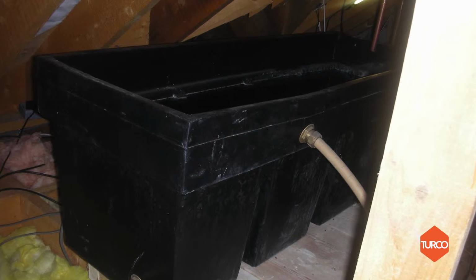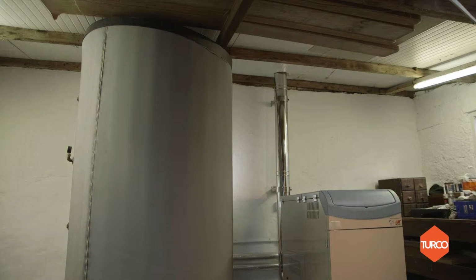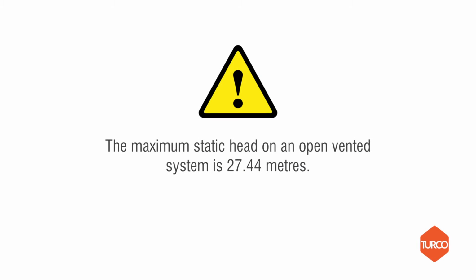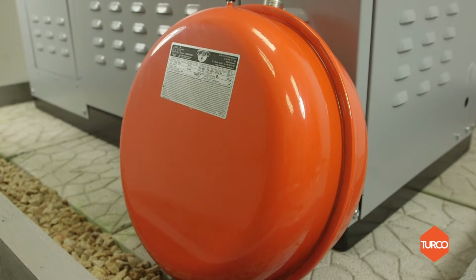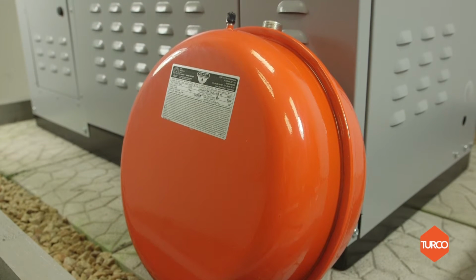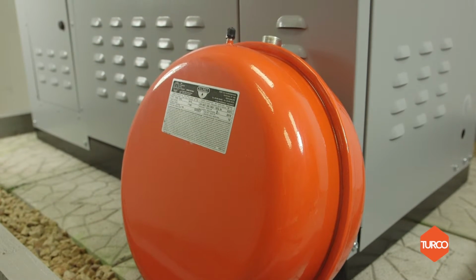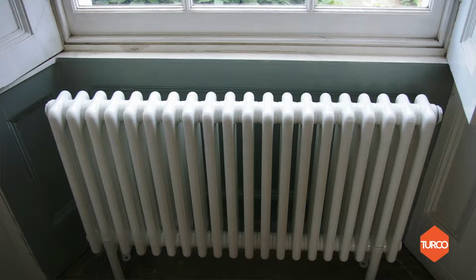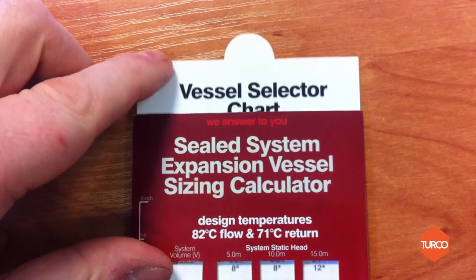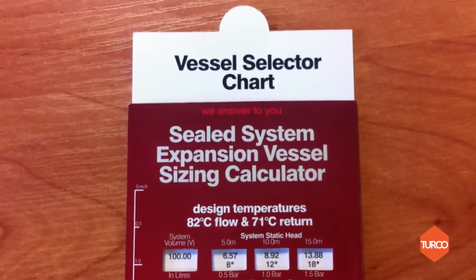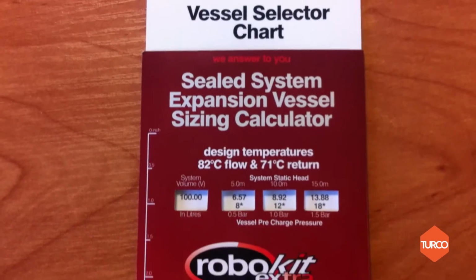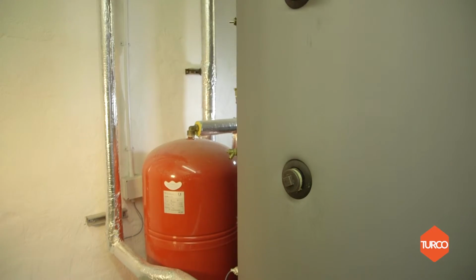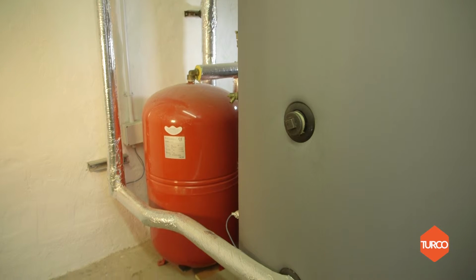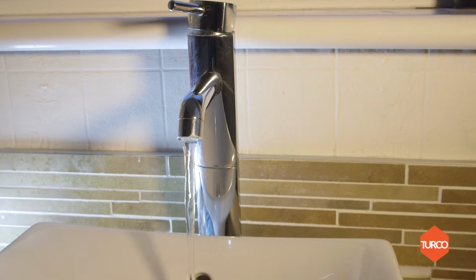The boiler can be plumbed into either an open vented or sealed pressurized system. The maximum static head on an open vented system is 27.44 meters. If on a sealed system, the expansion vessel must be installed as per the manufacturer's instructions and based on the water capacity in the boiler and the entire heating system. Failure to size the expansion vessel correctly may cause the boiler to leak over time and invalidate your warranty. A minimum 18-litre vessel is recommended plus additional expansion for the heating and domestic hot water.